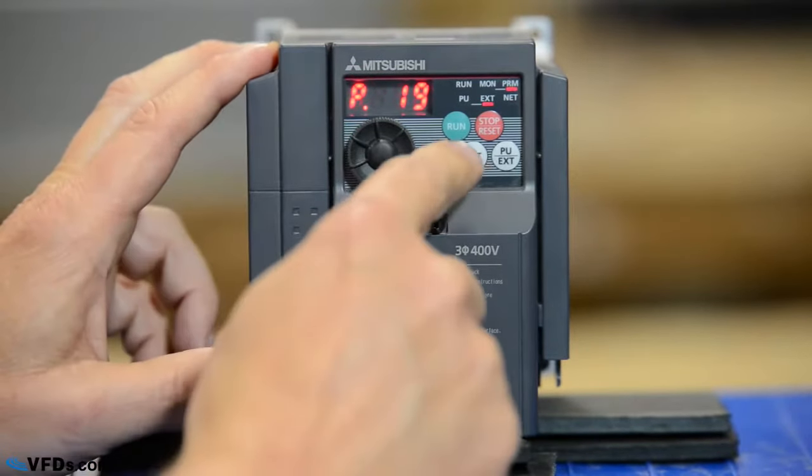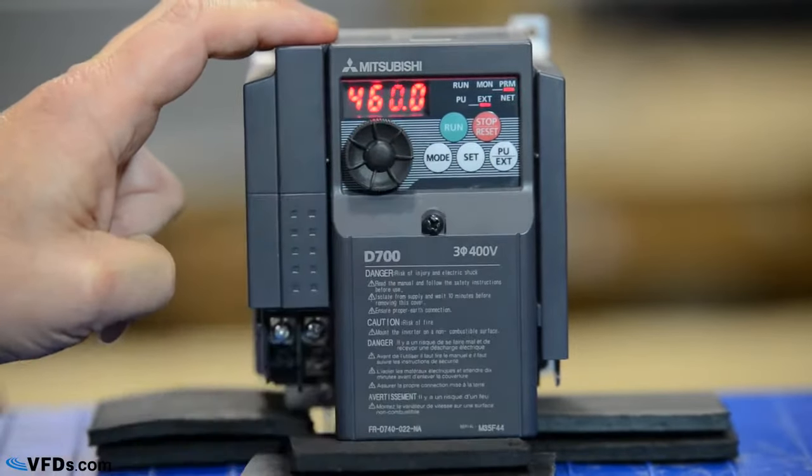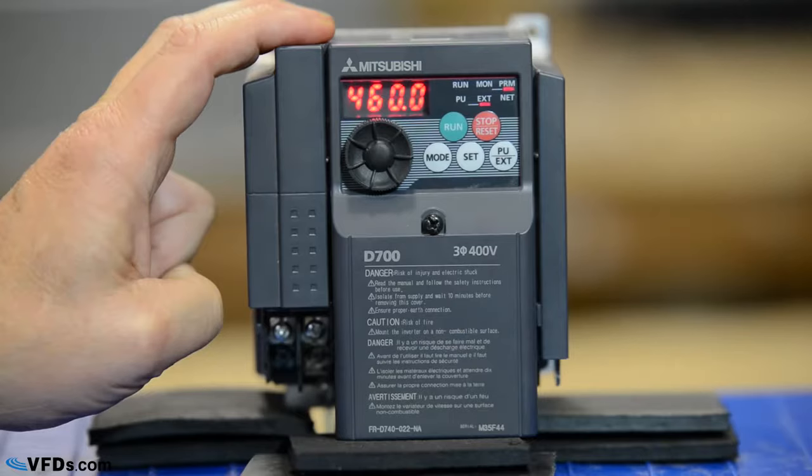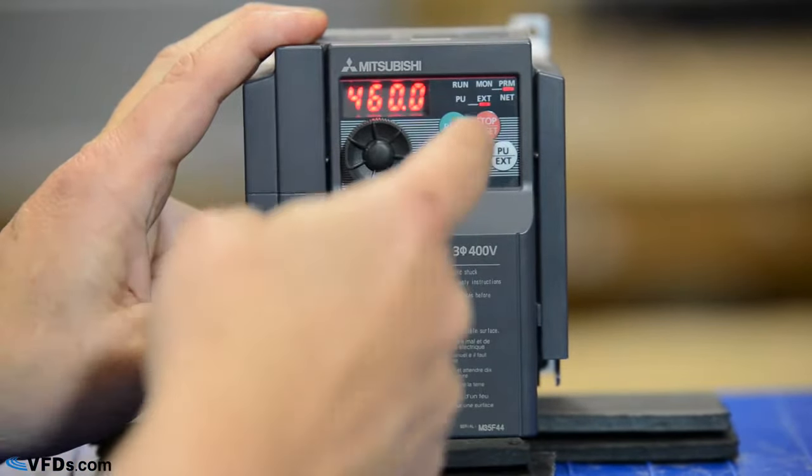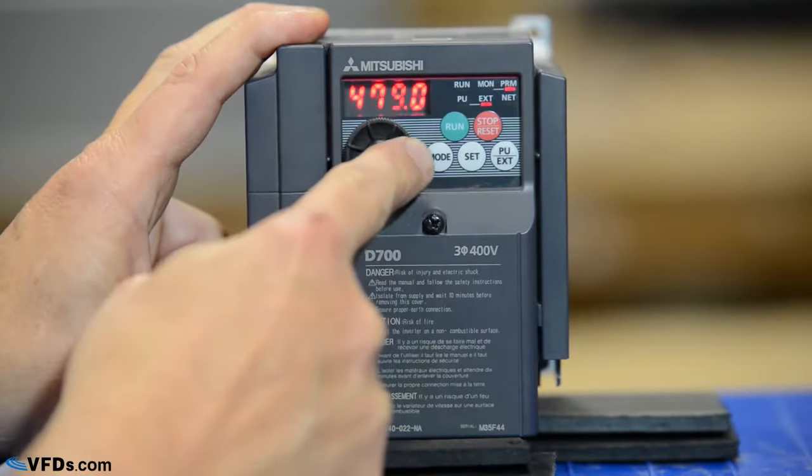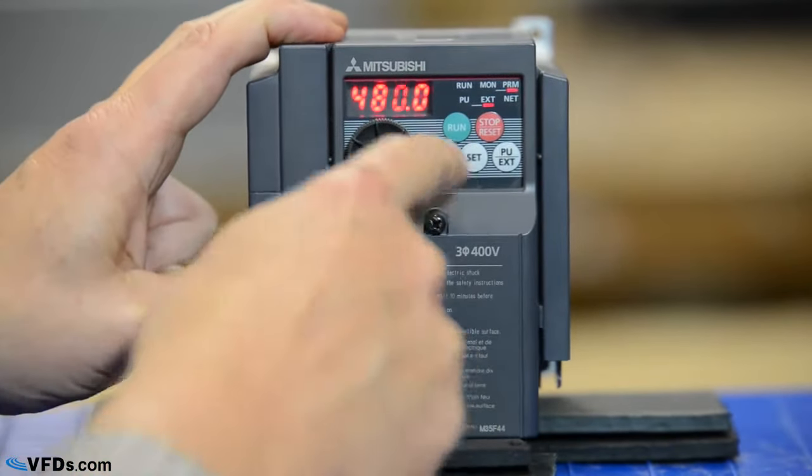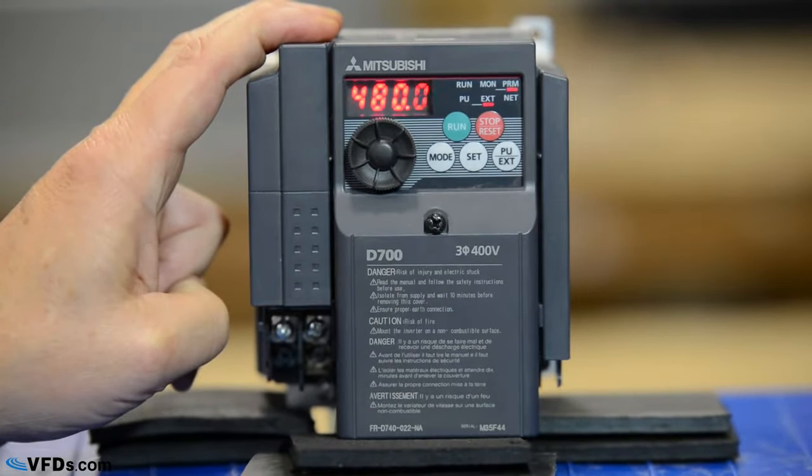So we're on parameter 19. We press set and that is set for 460 volts. Maybe I want my motor set for 480 volts. I simply change this to 480 volts, and when I get to 480 I simply press set again and it blinks to show me that I've changed that setting.